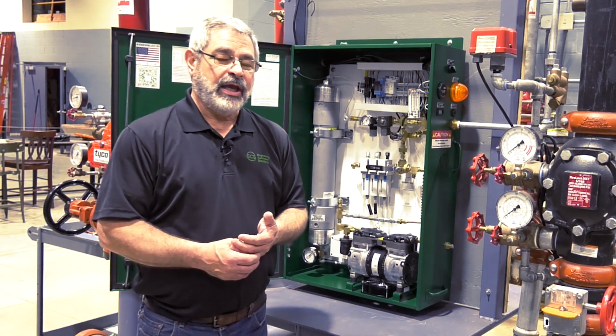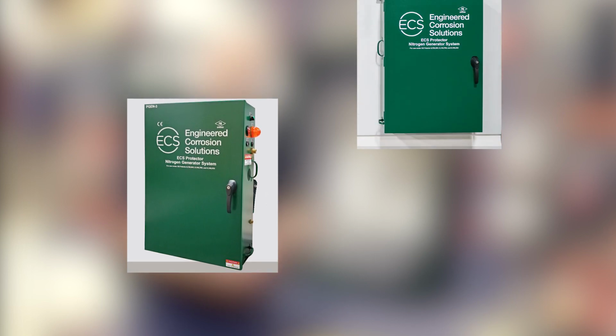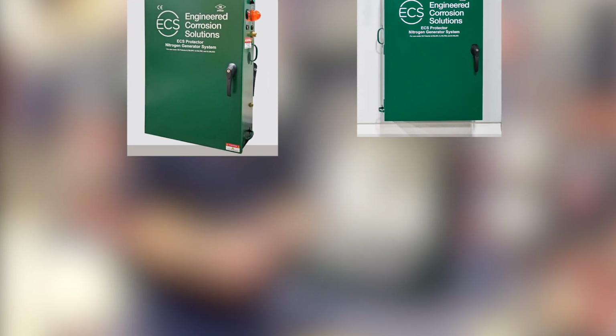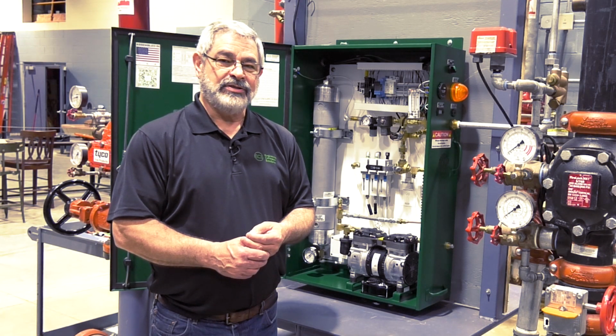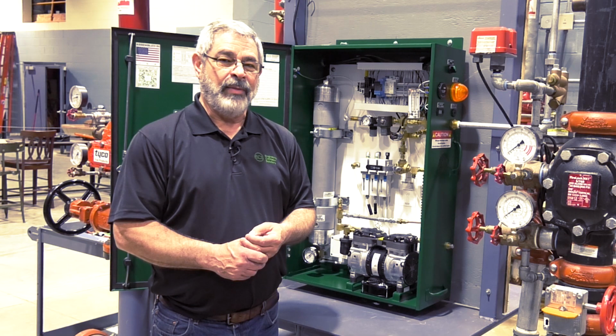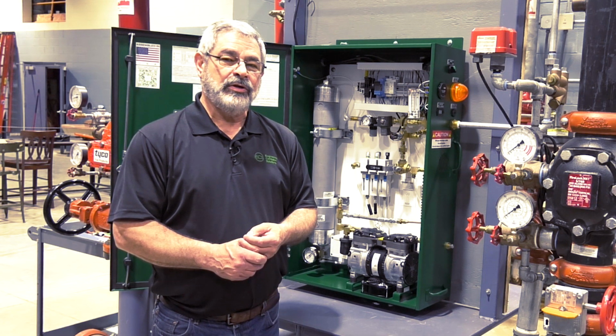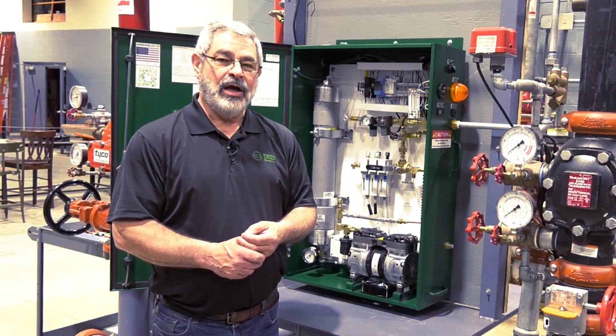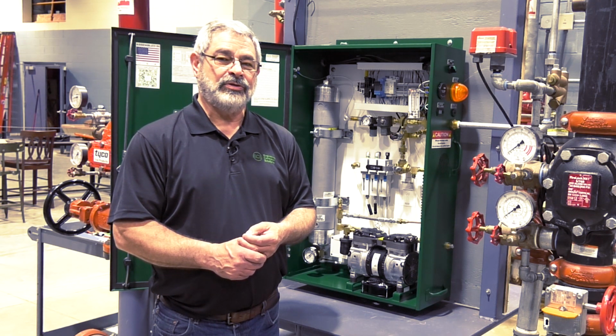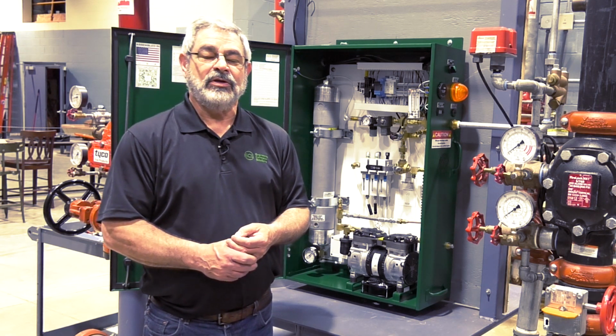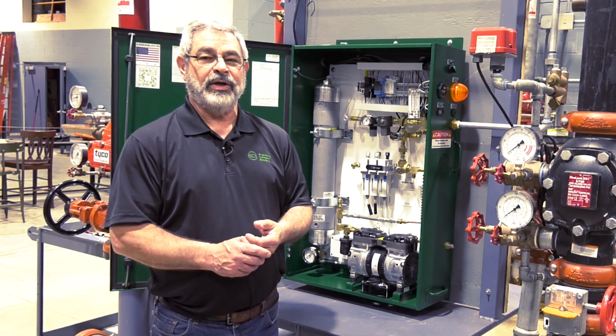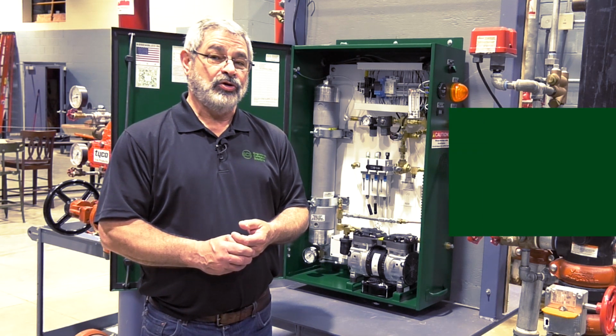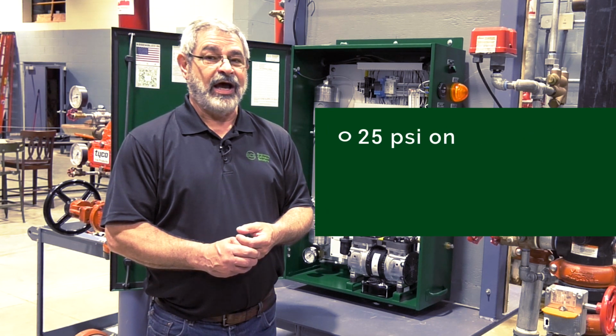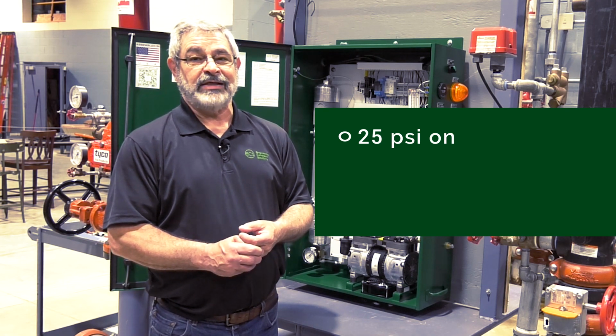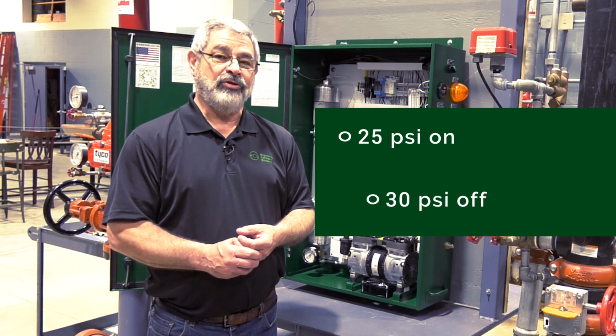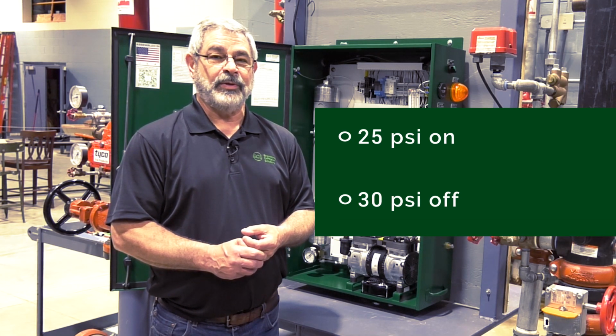parameters. In applications where you're using a PGEN 3 or a PGEN 5, with a single sprinkler system, NFPA will allow us to operate that unit without an air maintenance device. In those applications, we're going to use the nitrogen generator to become the air maintenance device or control the pressure in your sprinkler system. In the application where you want your supervisory gas pressure to be 30 PSI, we would set the turn on pressure at 25 PSI, 5 pounds below your supervisory gas operating pressure, and the turn off pressure at 30 PSI, so we can control that pressure within your sprinkler system.